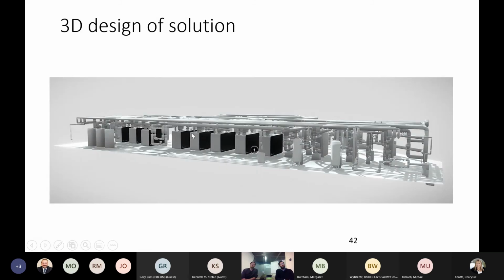Here you can see a 3D design of one of these systems. This is for a large IKEA warehouse in Sweden, where we have 5 base load heat pumps — 3 of them run for both heating and cooling generation. Their cooling peak load is much higher than their heating peak load, so the last 2 are primarily installed for cooling, but because they're so close, we hook them up also for heating. This gives them massive redundancy in the system, which is always a very nice thing. Then you have the hot water production heat pumps over here, and of course a lot of piping to connect it all.